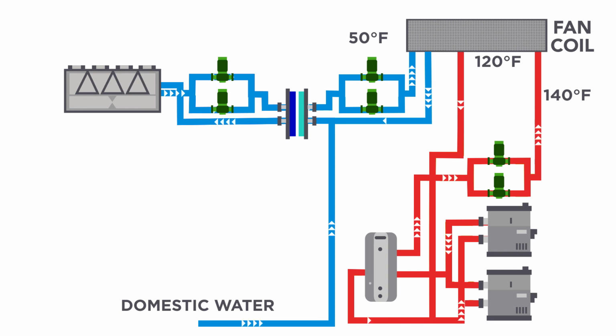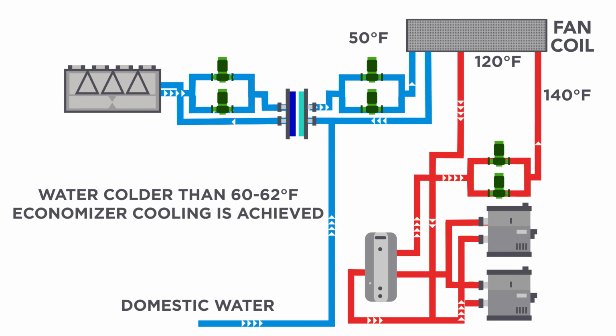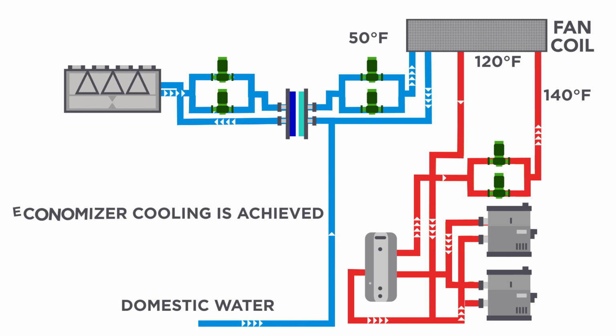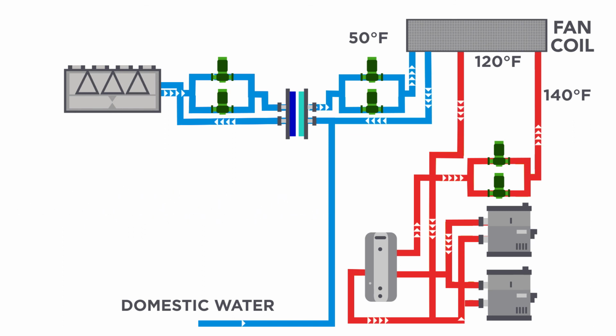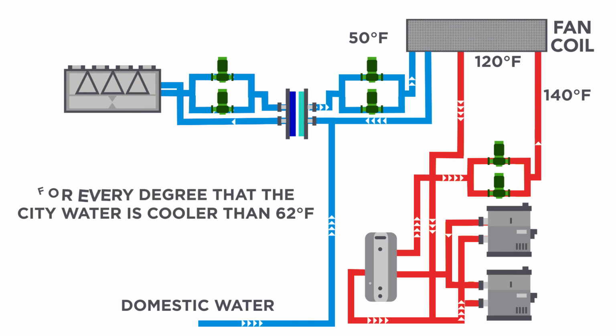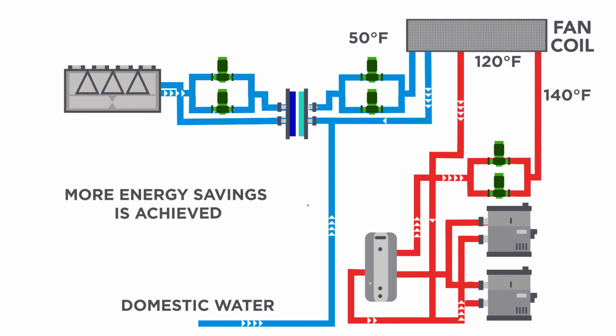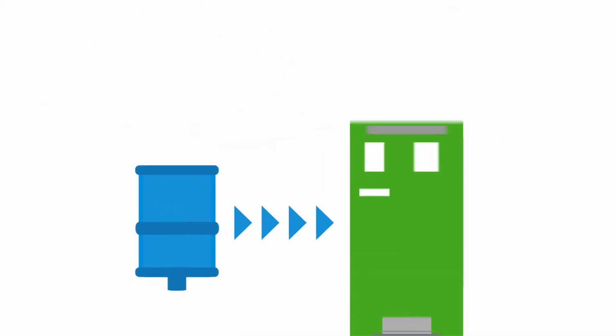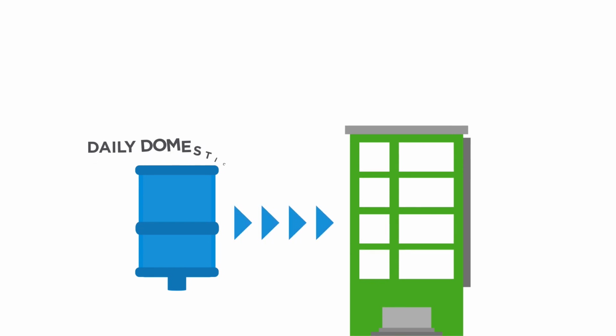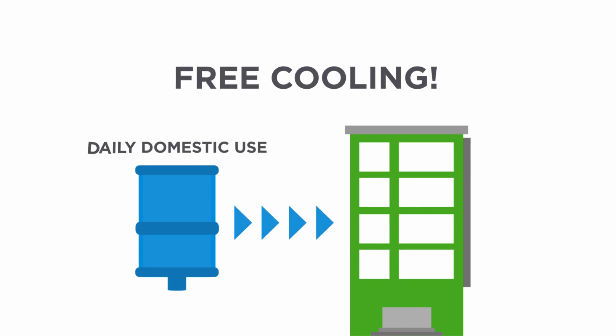In areas where water from the local municipality coming into the building is colder than 60 to 62 degrees, then the chiller isn't required to work as hard and economizer cooling is achieved. Economizer cooling is simply the use of water temperature supplied to the loop from the city supply that reduces the need for mechanical cooling. For every degree that the city water is cooler than 62 degrees, more energy savings is achieved. In fact, with lower city water temps, every gallon of water introduced into the building to be used for daily domestic use offers free cooling to the space.